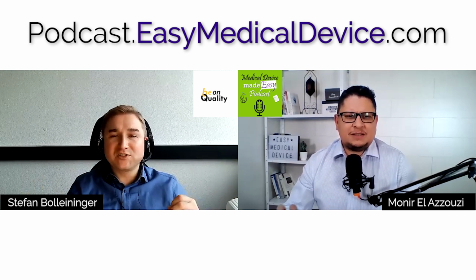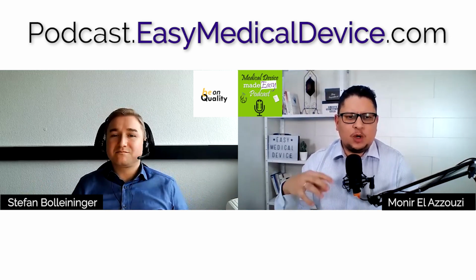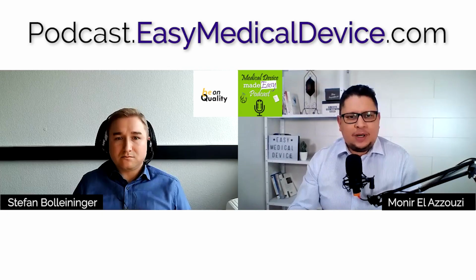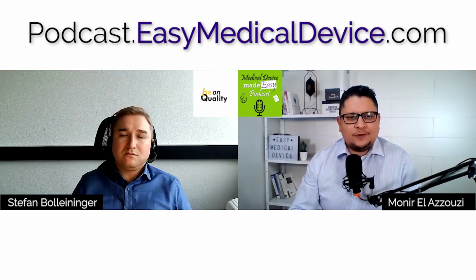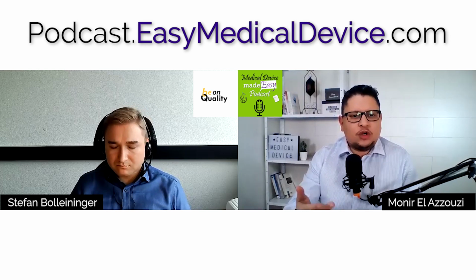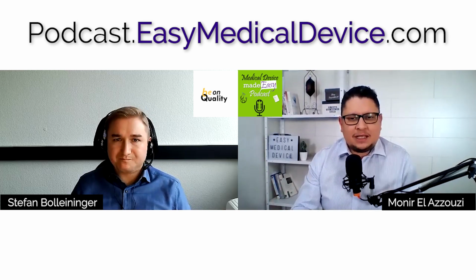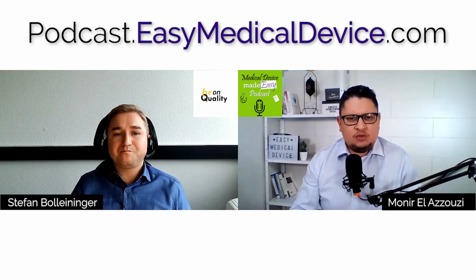Performance evaluation is mainly the fact that you are claiming some performance for your device, so then you have to prove that those performances are correct. It's mainly also something that we are doing for non-medical device products. So for every product, as soon as you claim a certain performance, you have to back it up with some data to prove that what you are saying on your box or IFU or whatever is correct. So safety and performance, no clinical performance at all, but some performance of what the device is doing.